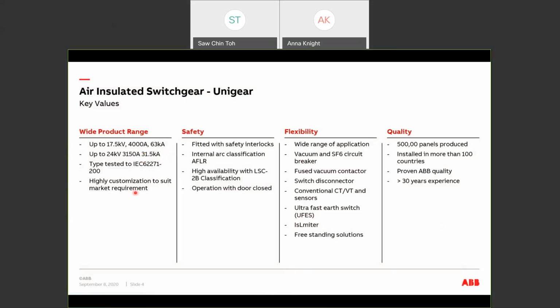So UniGear will offer a single user interface with the same operational and maintenance procedure. The spare parts inventories can also be kept at a minimal with the same type of cubicle. The switchgear is also fully type tested to IEC 62271-200 standards, and is highly customizable to meet your market requirement.